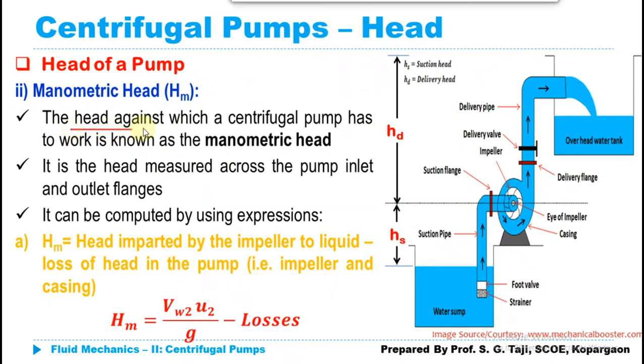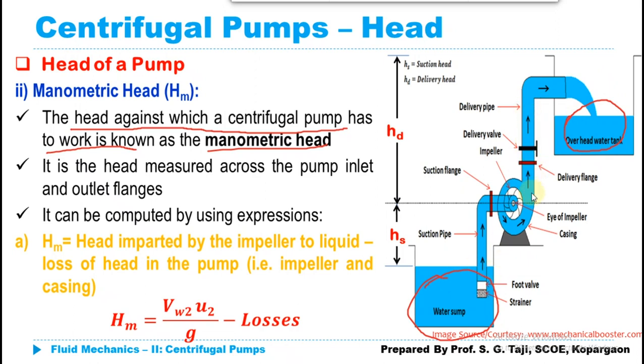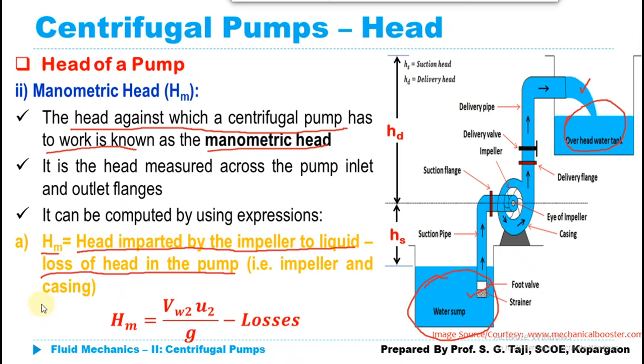The next head is the manometric head — the head against which the centrifugal pump has to work, generally measured across the pump inlet and pump outlet. It is the head which needs to be developed to deliver water from the source to the overhead tank or desired location. The manometric head is given by HM equals head imparted by the impeller to the liquid minus loss of head in the pump, that is in the impeller and the casing.